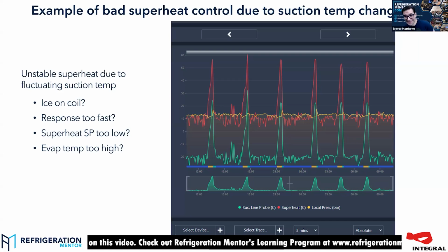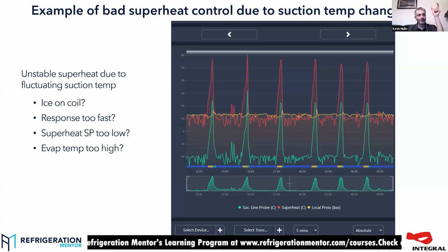No, definitely not. And the problem with that is that because you'll have a multi-pass coil with 5 or 6 inlets on it, that first bit of the coil is going to do no evaporation whatsoever.